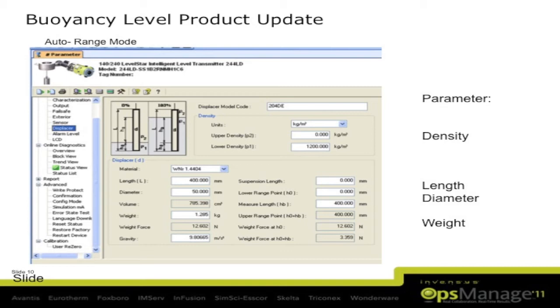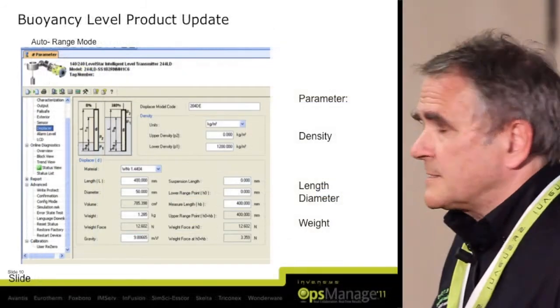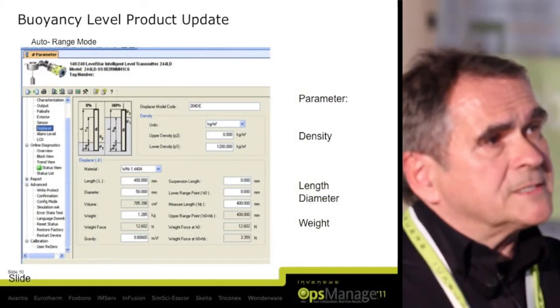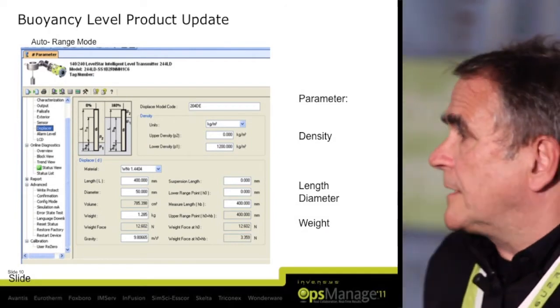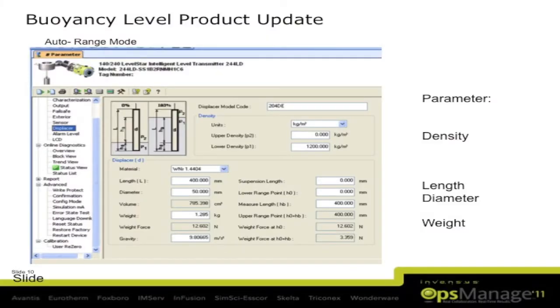Here you have the information from the displacer element. This is the material of the displacer element, the length, the diameter. Out of the length and the diameter, a volume is calculated. You type in here the weight of the displacer, and the weight of the displacer including the chain. Then the weight force is calculated. You have the length of the chain, and maybe if you have an elevation of the displacer, you can also adjust this, if it does not go to the full range or not to the 0 point. As an elevation, all this is possible on this page. If you type this in, the displacer is re-ranged.